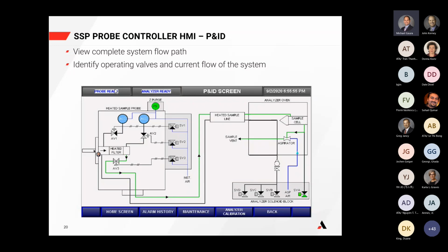So we can see that right now the probe is in ready mode, the analyzer is in ready mode, they're both in sampling mode. We don't see any alarms or issues here. The sample is coming through the probe and through the heated filter. It's being routed through the heated sample lines all the way to the sample cell. And then it's either being vented out through an aspirator. In this case, it is being vented out or returned to some safe location.